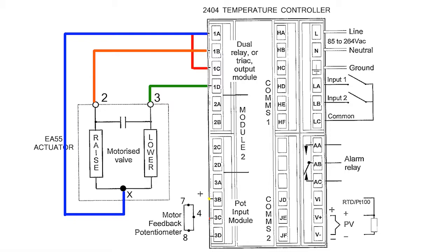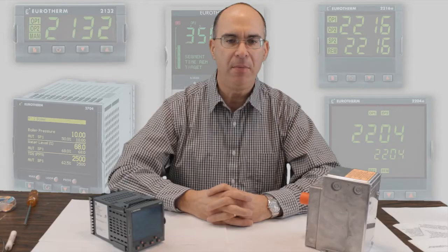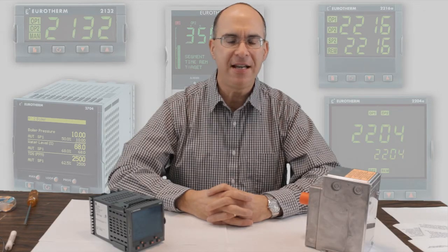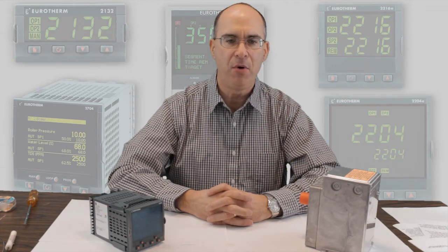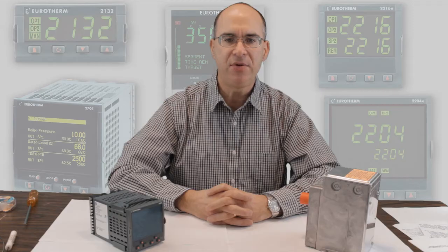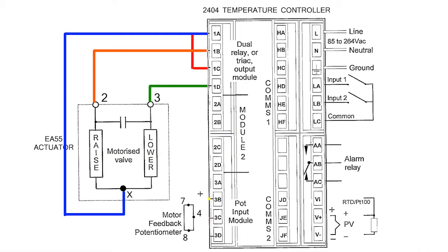As an option, a slide wire potentiometer input module can be installed in the temperature controller to measure the slide wire feedback position of the motorized valve actuator. To use this option, wire terminal 3B of the temperature controller to terminal 7 of the motorized valve actuator.